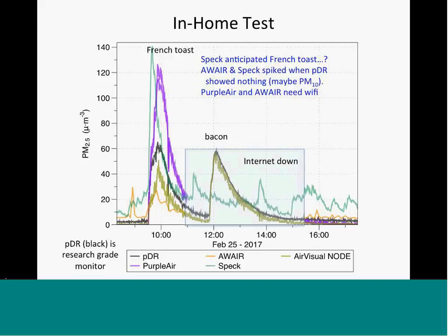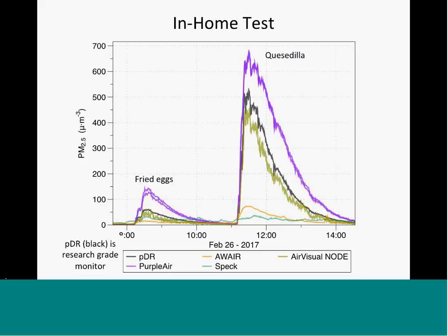And this is one of the challenges of using devices that are internet connected, is that sometimes if they don't have internal storage that you can access later, without an internet connection, they don't store the data. And this might be a bit tricky if we're trying to use these as control devices, because we do become internet dependent. I will say, though, that these devices do automatically detect when they have internet access again and turn themselves back on, if you will, and automatically start logging. But if we're going to be dependent on an internet connection, that's something to be thinking about if we're considering the reliability of these devices for control purposes.